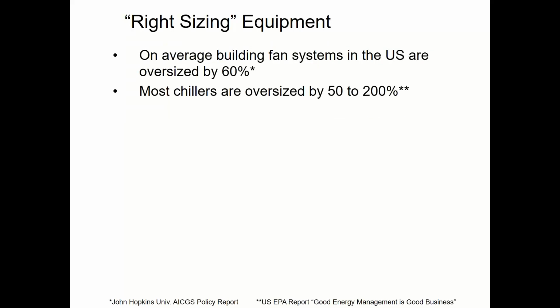So as part of that code, we're looking at sizing and efficiency of these package systems. If you were not aware of it, most systems in the United States are oversized, and they are grossly oversized. This example is talking about fan systems in the U.S. that are oversized on average by 60%. I'm sure there's somewhere out there a fan that's perfectly sized, but there's a bunch of them out there that are probably 100% oversized, and it's pretty dramatic. Same thing with chillers, same thing with boilers, rooftop units, fan coils, residential furnaces. Literally 100% of systems are oversized.